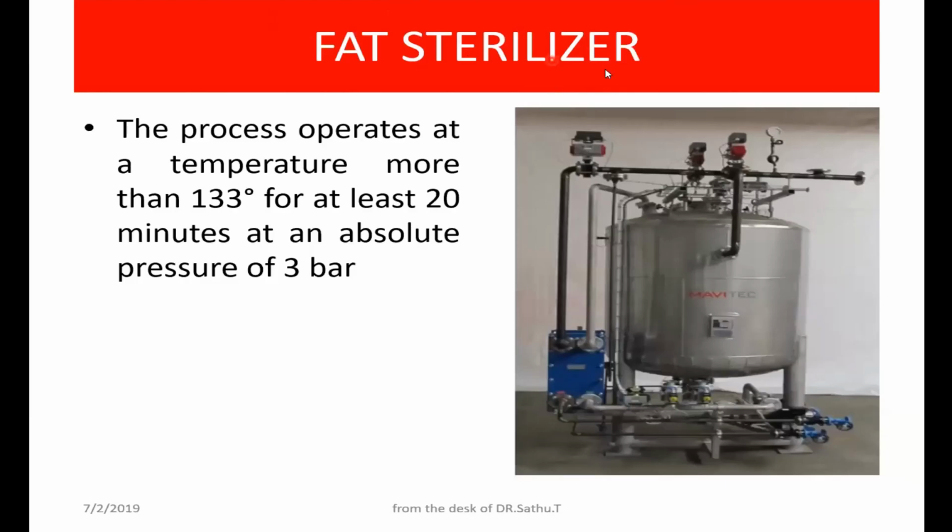So this is a fat sterilizer. If you want to sterilize the fat, you can use this fat sterilizer, where the process operates at a temperature of more than 133 degrees centigrade for at least 20 minutes at an absolute pressure of 3 bars. That can also be done, fat sterilization.